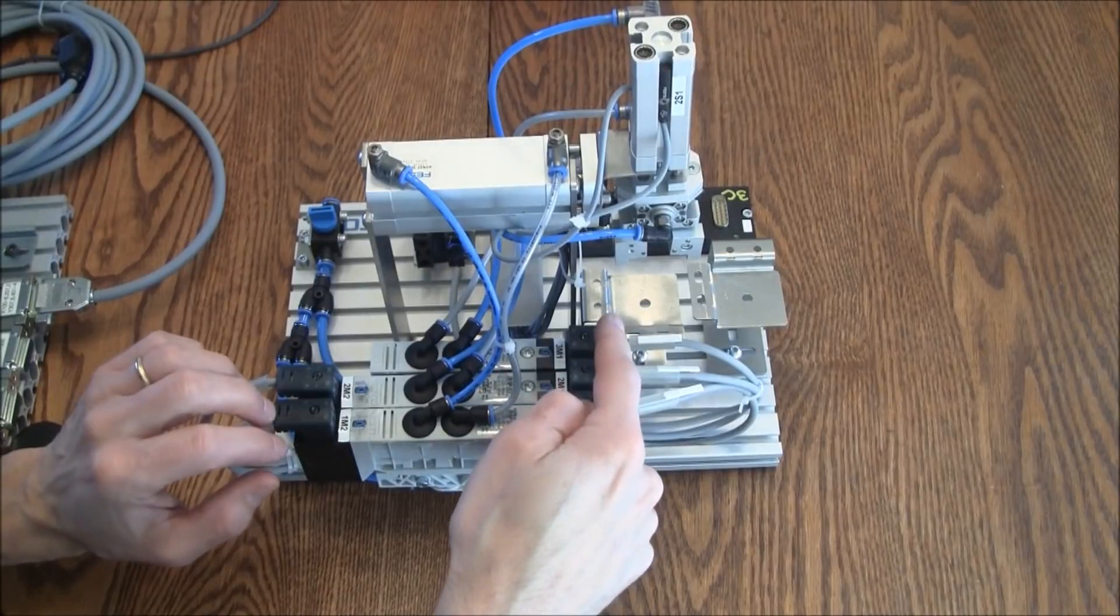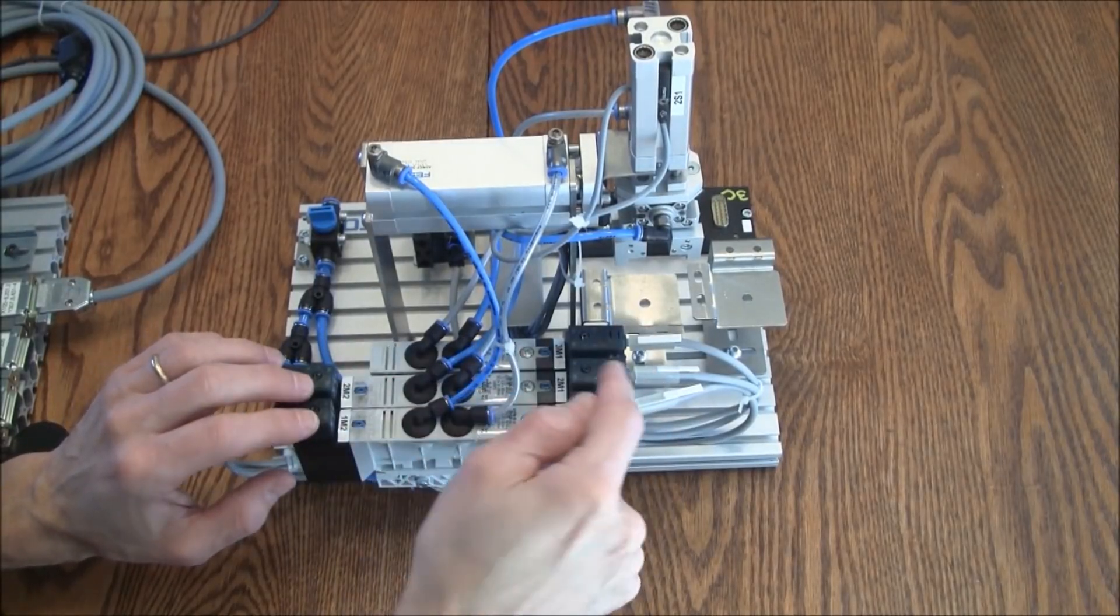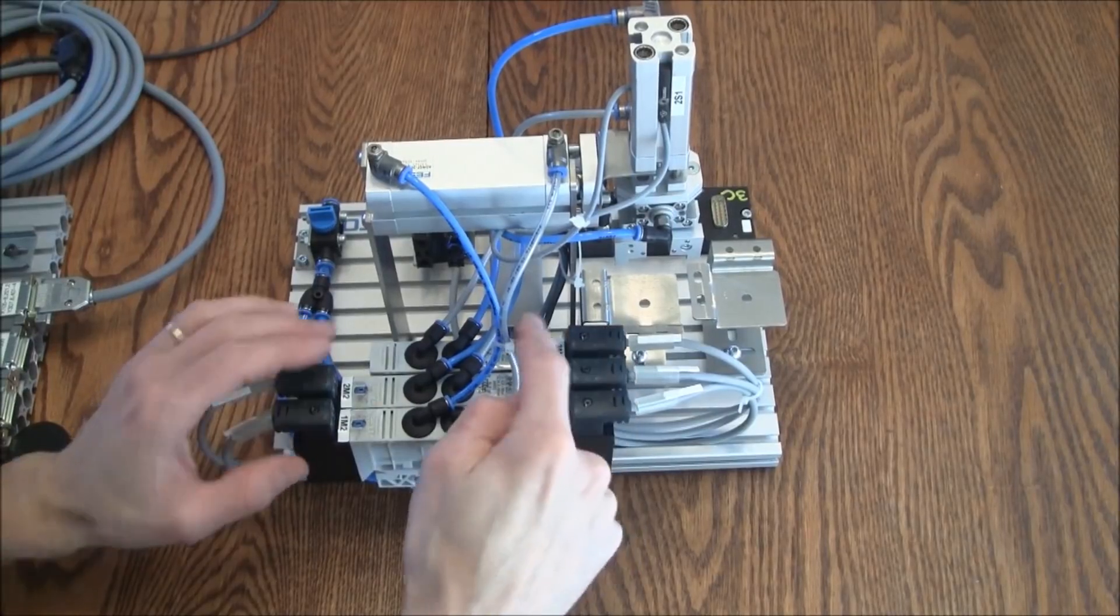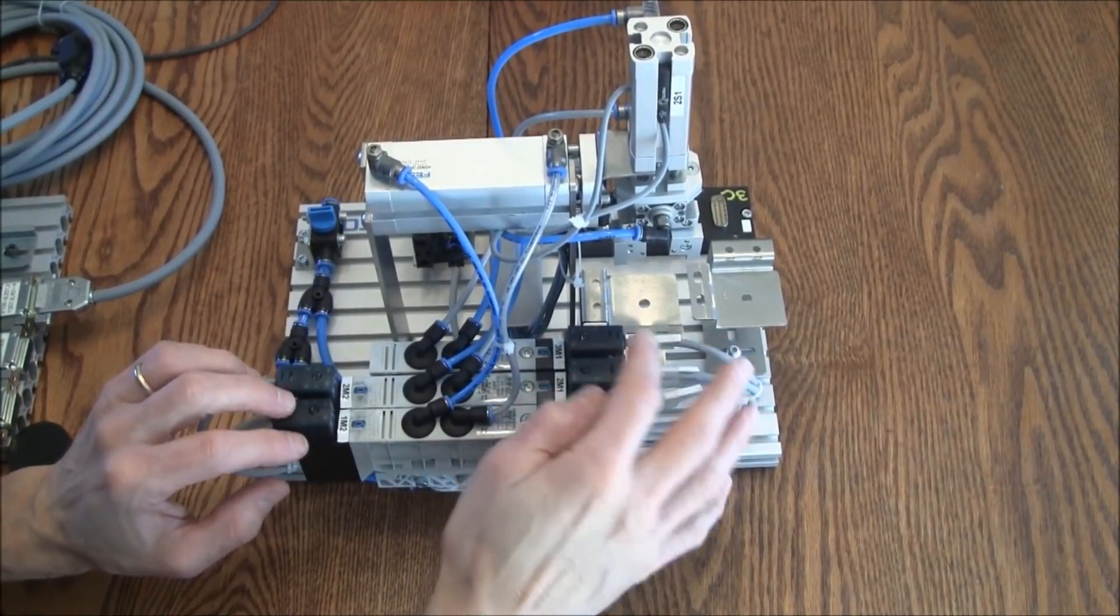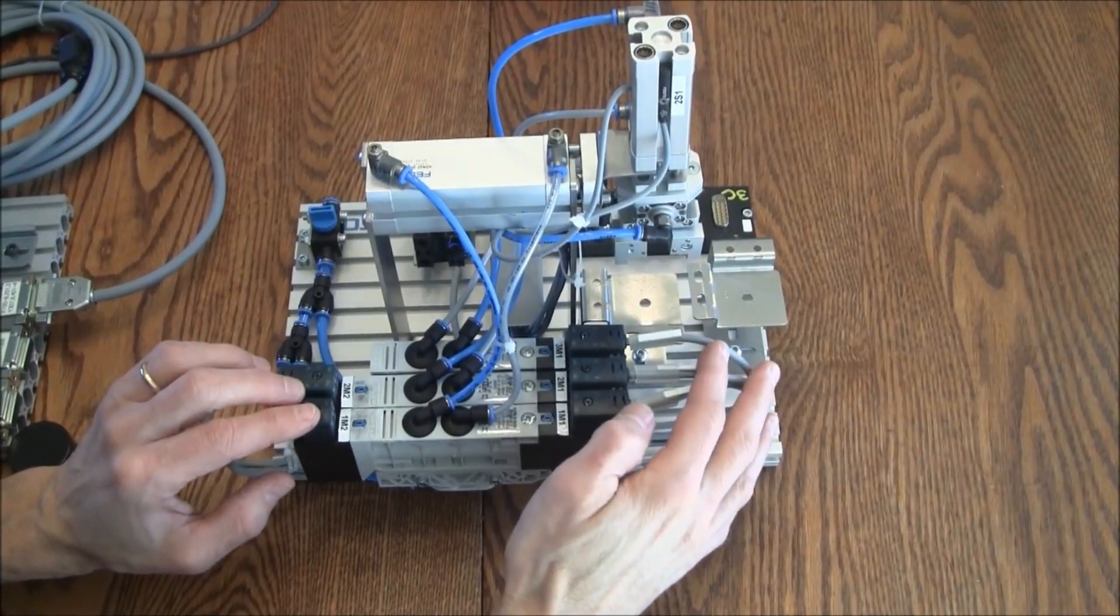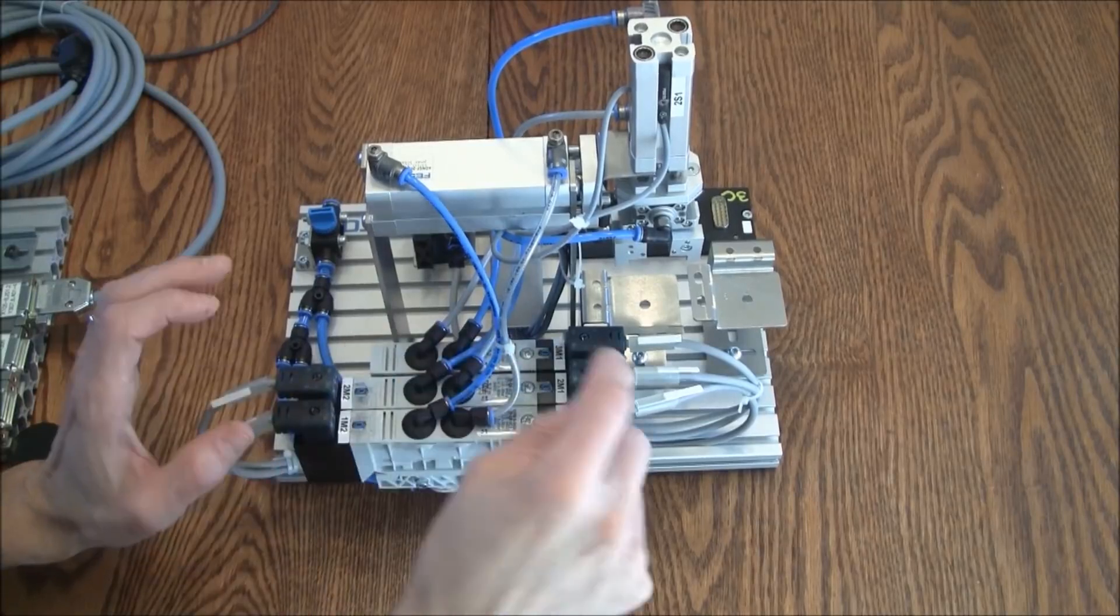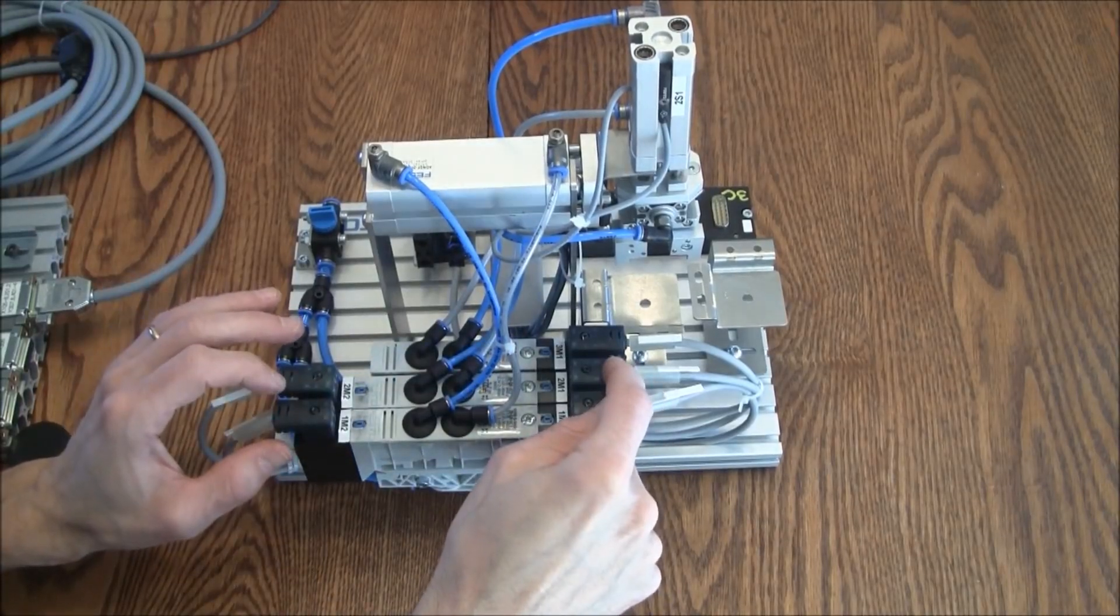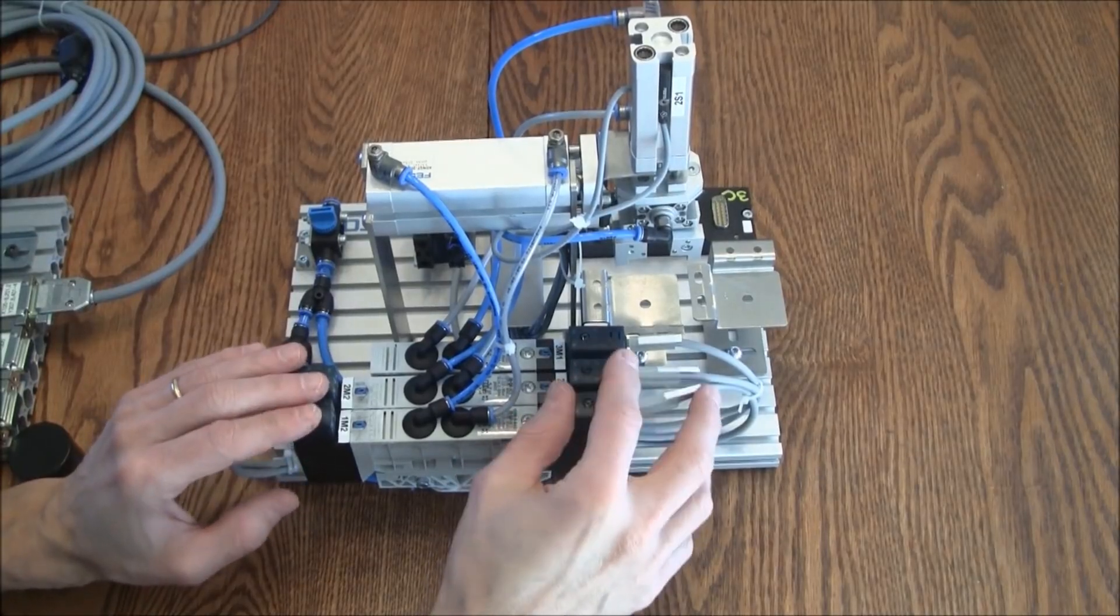One reason is, obviously if we're using single solenoid controlled valves, the valve is going to be cheaper because we only have one solenoid on it. It'll be cheaper. Also, we're using fewer I/O. I only use one output to control one cylinder, whereas these take two outputs to control a single cylinder. So why use the double?